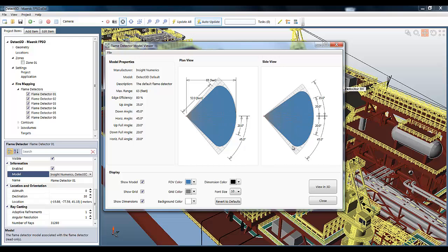Looking at the plan view first, we can see the maximum range, which for this model is 65 feet. We can also see that the horizontal viewing angle is 45 degrees in each direction. The 20-degree number here represents the viewing angle where the detector's range equals a maximum range. In other words, it can see the full 65 feet from 0 to 20 degrees, but beyond 20 degrees, its range reduces. This is typical for most flame detectors where their off-axis range is less than the on-axis range.